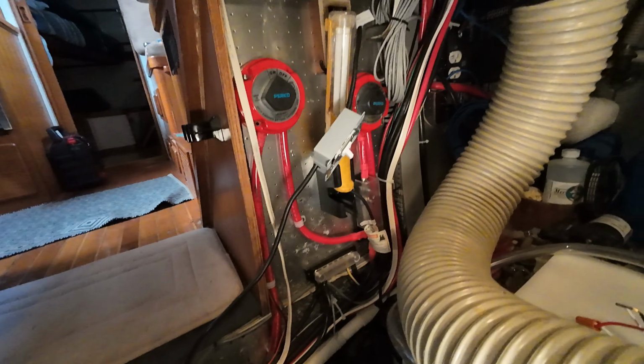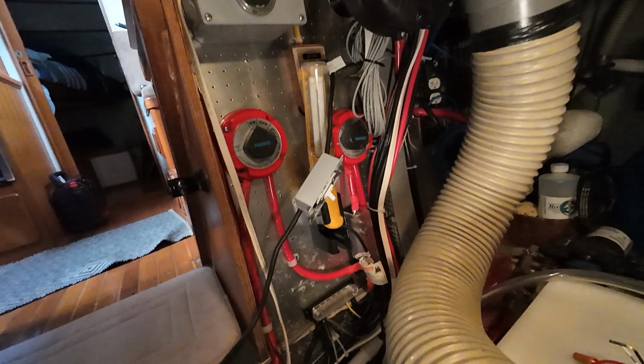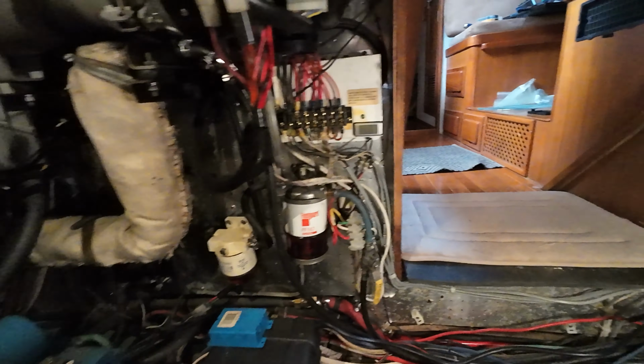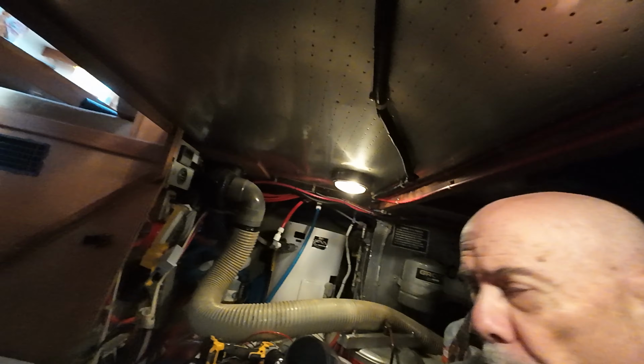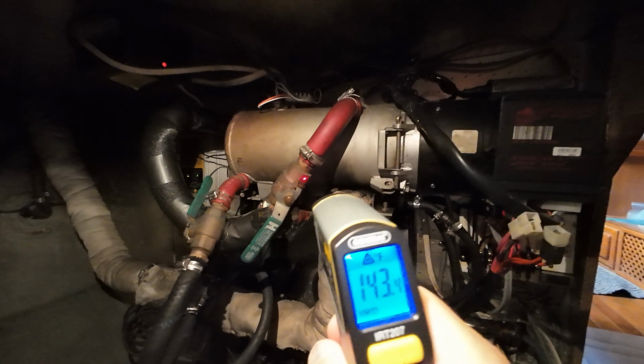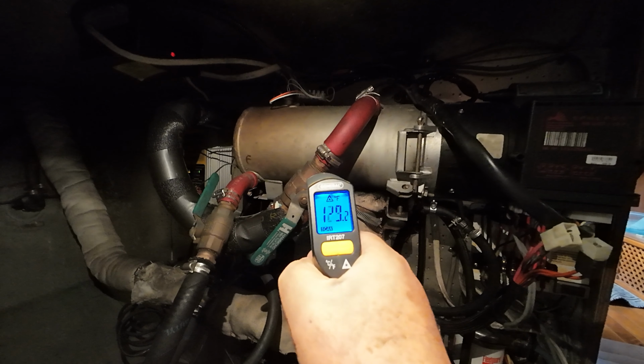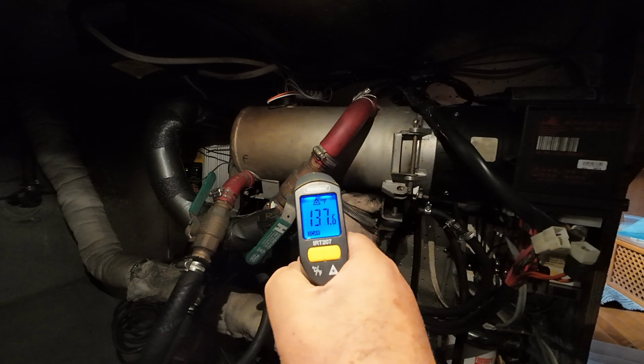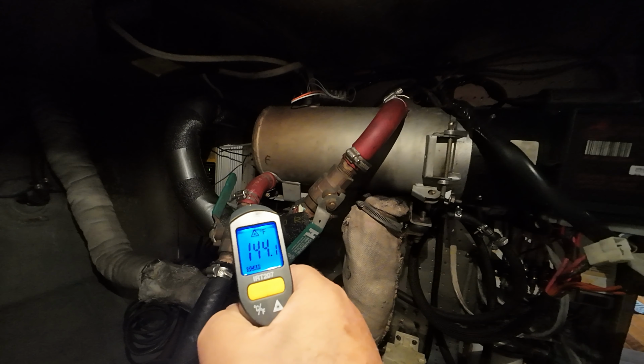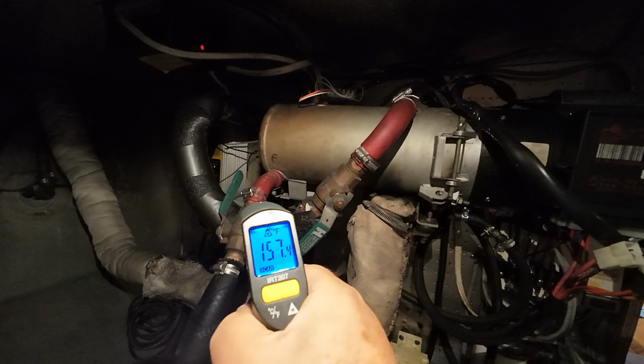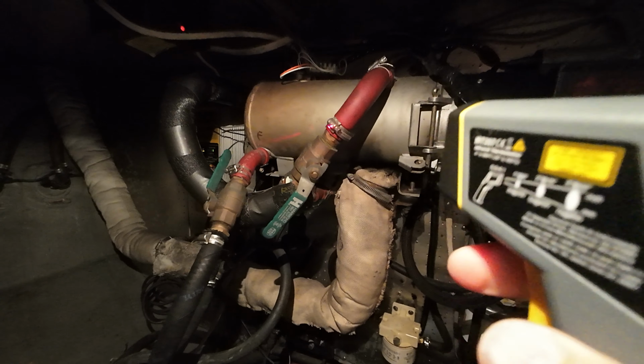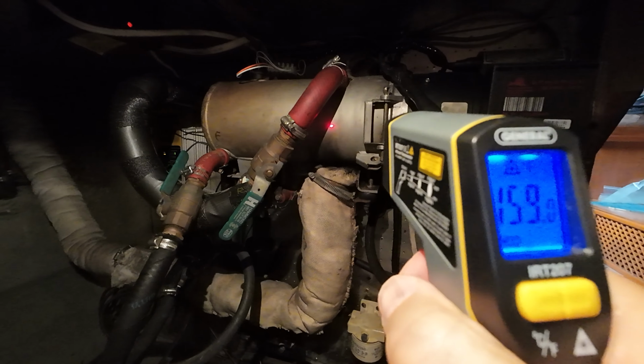But I have temporarily jury-rigged the pump to be on a switch over here so I can run it manually. And here's what's weird. Right now the pump is cycling. If we check the temperature on this guy right here, we're at 130 degrees, 137 degrees. If we check this, we're at 158. So we get to about 165 and then the unit shuts off.